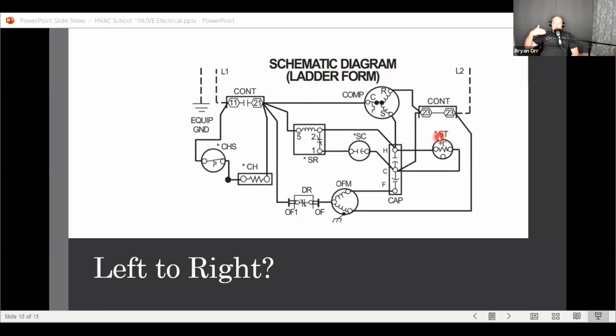But when we're talking about electrical circuits, if there is a path, then electrons are going to move across that path, proportional to the resistance in that circuit. So you look at resistance, you look at voltage, and that tells you how much current is going to move across that path. You sell yourself short when you only think in terms of left to right, because in a 240 volt circuit, it's also coming from right to left.